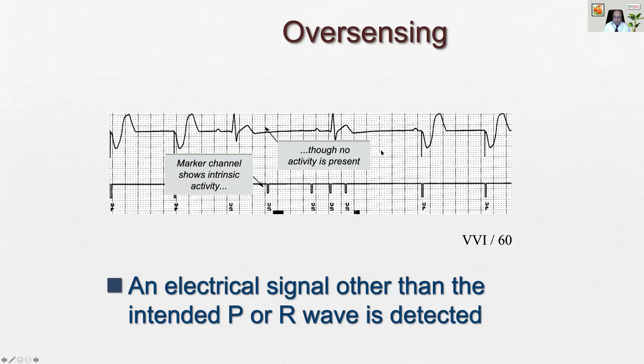So, for example, this is the intracardiac electrogram, and we have, say, the P wave here, the QRS complex, and the T wave. If we keep a high sensitivity, which means a lower value of, say, 1.25, then a lot of electrograms can be sensed. If we keep a somewhat lower sensitivity, 2.5 is considered lower sensitivity, because now only electrograms which are very tall can be sensed. So it has become lower.